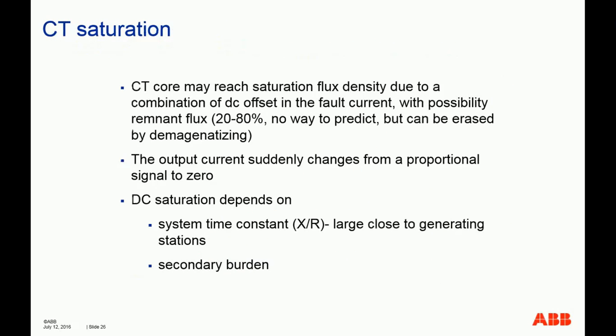So, CT saturation. The CT core may reach saturation flux density due to a combination of DC offset. DC offset actually is the main cause of CT saturation, with possibly the residual flux that's already contained in the CT, which makes the CT more prone to saturation. So once the CT is saturated, or slightly saturated, or begins to saturate, the output current will suddenly change from a proportional signal to a reduced amount. And if it's completely saturated, it will be reduced to zero. So as you can imagine, if the secondary current becomes zero because of CT saturation, then your protective relay, no matter what kind of protection, will not accurately measure any current from that current transformer.